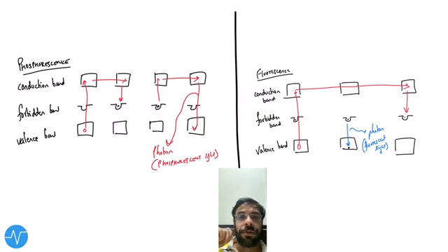Second, phosphorescence. Valence band electron moves to the conduction band and it falls to the forbidden band and remains there for a variable amount of time. If again a stimulus is given like heat or other stimulus, from the forbidden band to the conduction band and then directly it jumps from the conduction band to the valence band, this energy difference is given in the form of a photon or phosphorescent light. Where is this phosphorescence used? It is used in the principle of thermoluminescence dosimetry or TLD, which we'll discuss later. Therefore, phosphorescence emits light after a variable amount of time, whereas fluorescence emits light immediately.